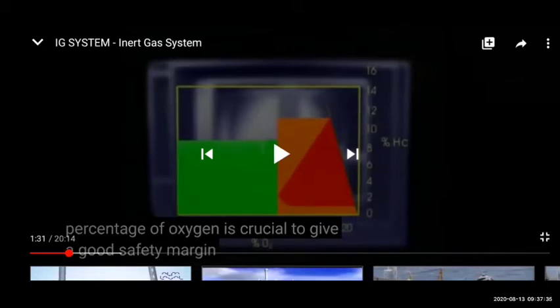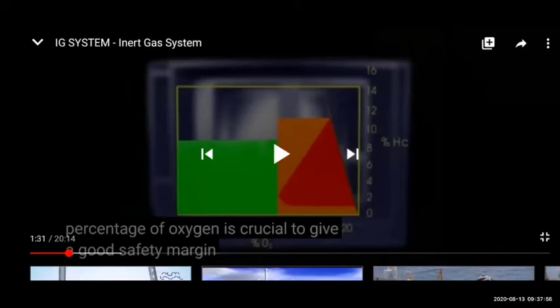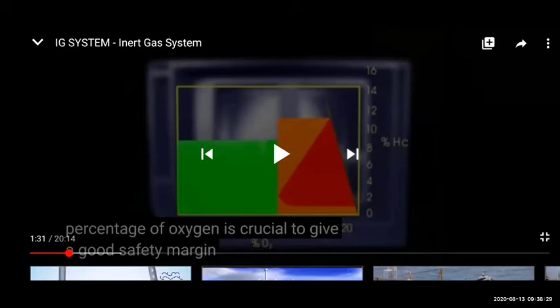In the flammability diagram, the flammable mixture is shown in red and non-flammable in green. Hydrocarbon ranging from around 1% to 11% in the tank combined with oxygen from 11% to 20% is a dangerous flammable atmosphere. If oxygen is less than 11%, it is non-flammable. If hydrocarbon is more than 11%, it is too rich — not flammable. If less than 1%, it is too lean. The upper explosive limit is 11% and the lower explosive limit is 1% for hydrocarbon.